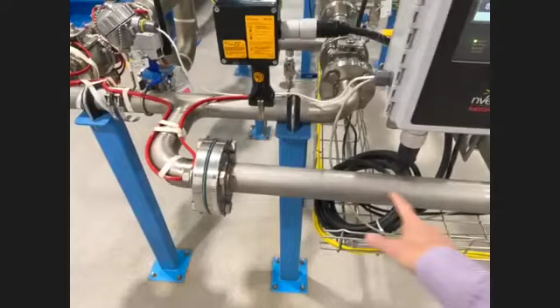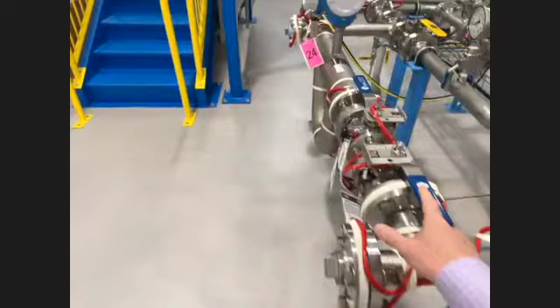What we would then do is choose from the selection of cables we have that is obviously a little bit higher than 4.3. We have a 5, 8, 10, and so on and so forth. So we would have a straight run of cable on a straight length of pipe. Now, when you come to something like a support, a flange, or a valve, there's obviously a lot more mass there. So that calls for additional heat. So that's why there is an actual wrap of cable. You would never want to go straight across with that cable. It just won't have enough output to keep that additional mass, valve, or whatever that is from freezing.